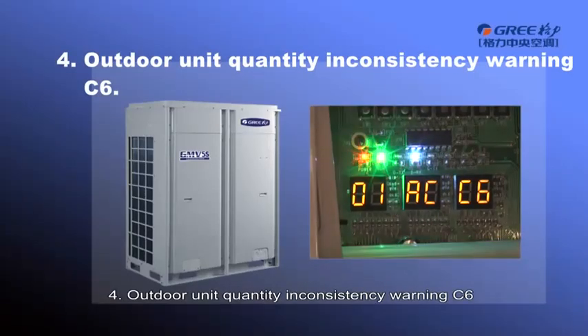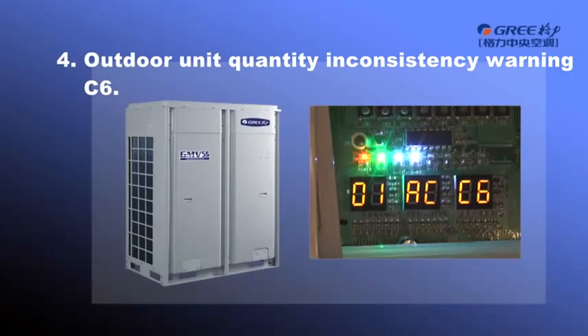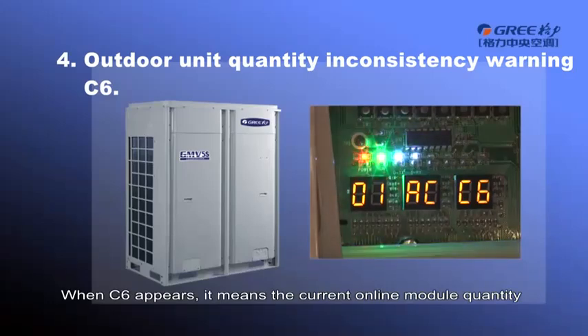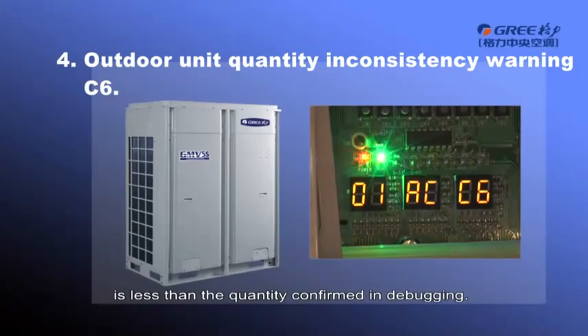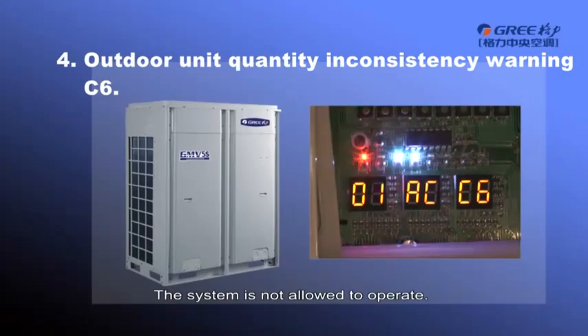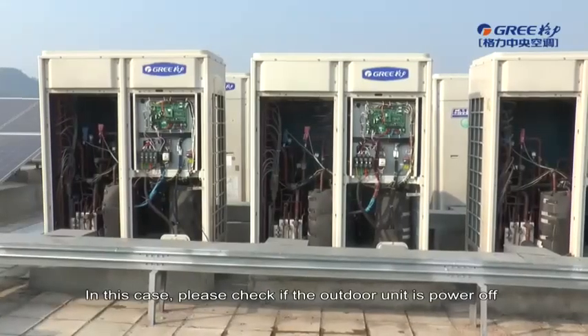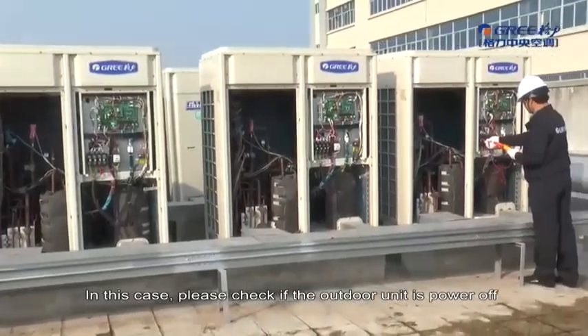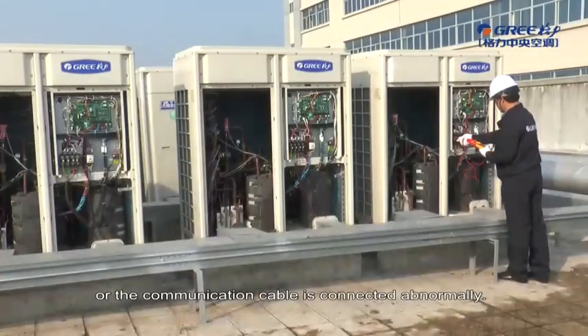Outdoor unit quantity inconsistency warning. When C6 appears, it means the current online module quantity is less than the quantity confirmed in debugging. The system is not allowed to operate. In this case, please check if the outdoor unit is powered off or the communication cable is connected abnormally.